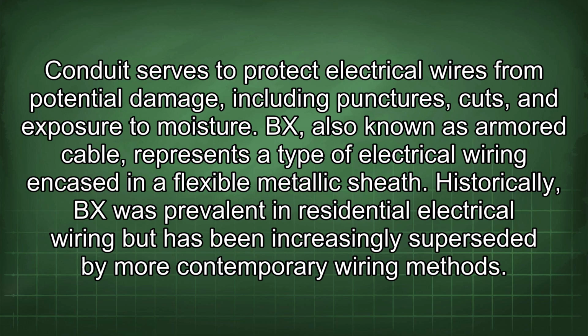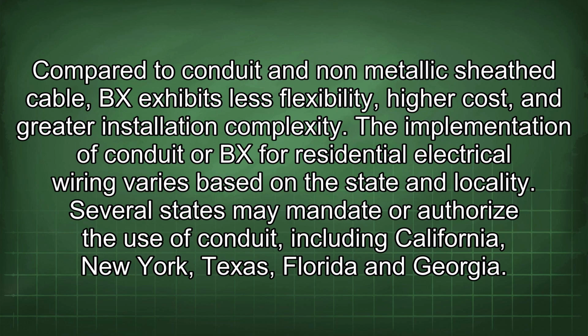BX, also known as armored cable, represents a type of electrical wiring encased in a flexible metallic sheath. Historically, BX was prevalent in residential electrical wiring but has been increasingly superseded by more contemporary wiring methods. Compared to conduit and non-metallic sheath cable, BX exhibits less flexibility, higher cost, and greater installation complexity.